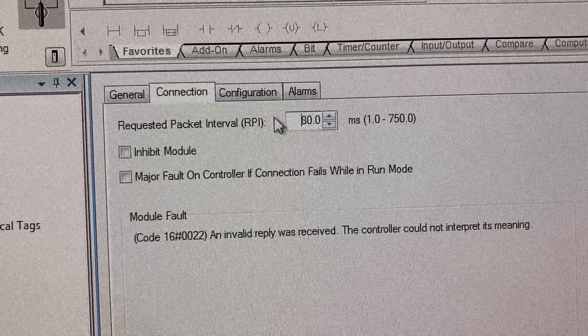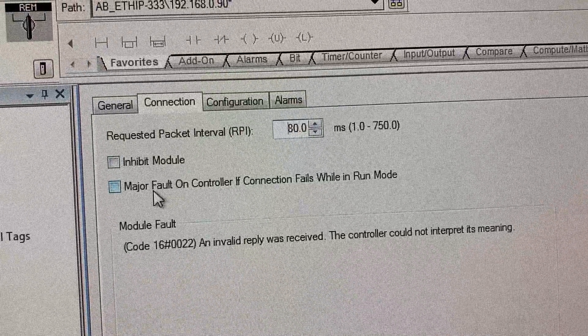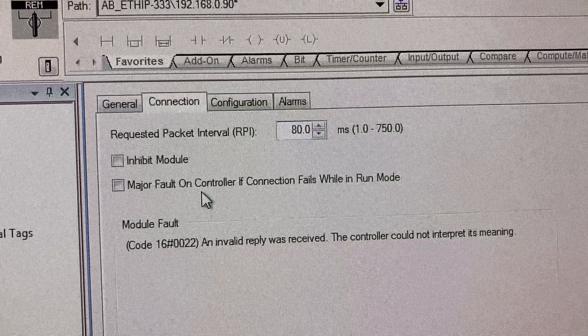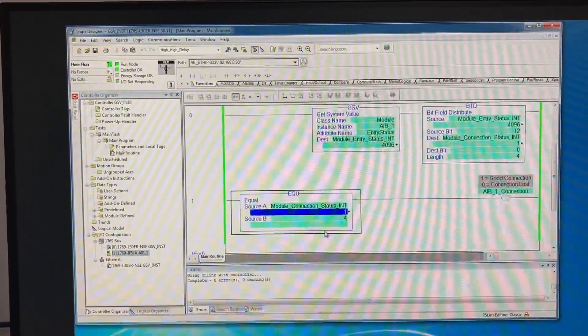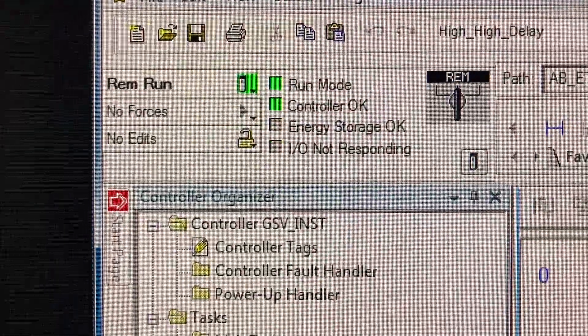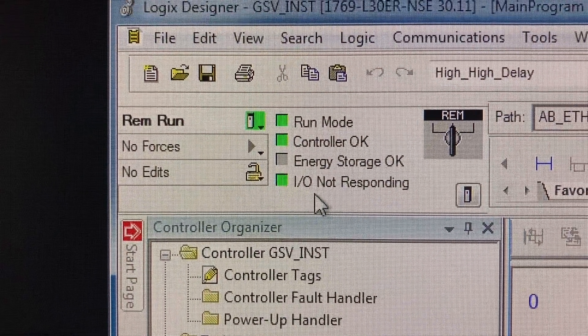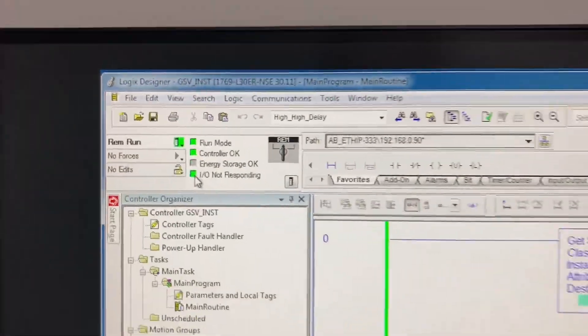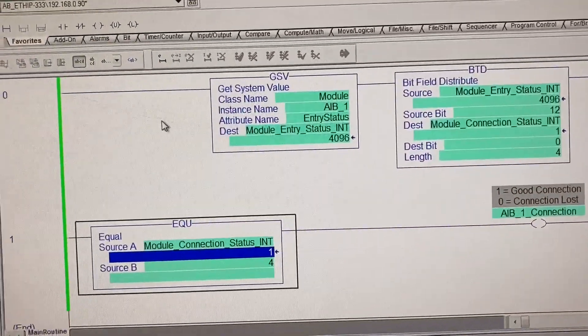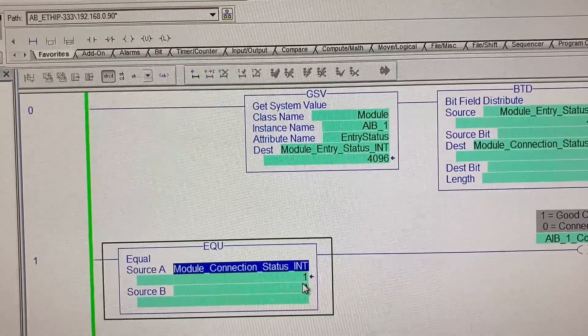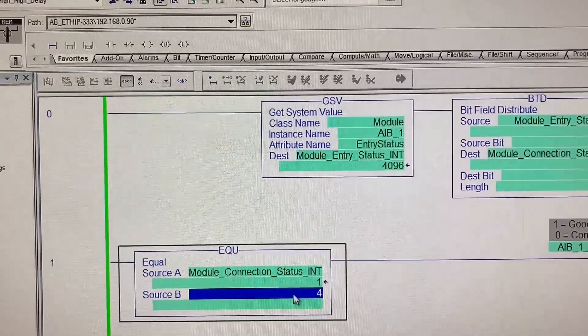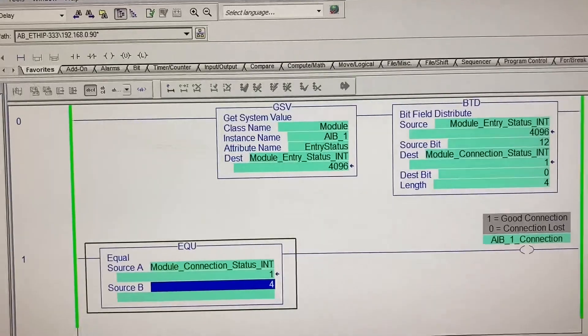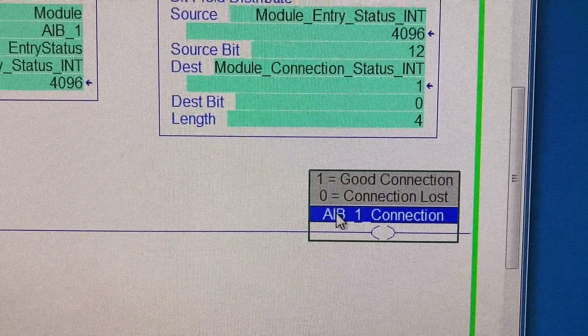Because this box is unchecked to prevent PLC major fault if it doesn't see the module. We are online with the PLC now. IO not responding, blinking green. The value here is 1, it's not 4. Connection is lost.